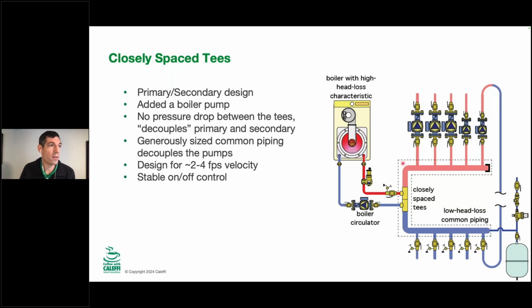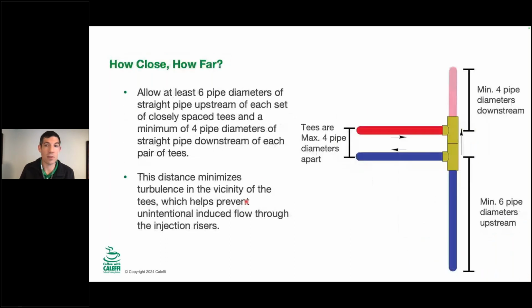So if you turned on these 5 pumps, this pump was off, but for some reason you have 4 GPM going through that, you missed something. There's something sizing-wise, piping-wise that's not right there. You're influencing flow to the left side of the equation. We don't want that. We want these to be truly separated so they can operate independently, and we move those gears out of conflict. So what we're looking for is a specific velocity to make that happen. If we make these T's too small, as an example, that could affect it. If we have 18 inches of pipe in between here, that can affect it. And I'll show some examples of that on the next couple slides too.